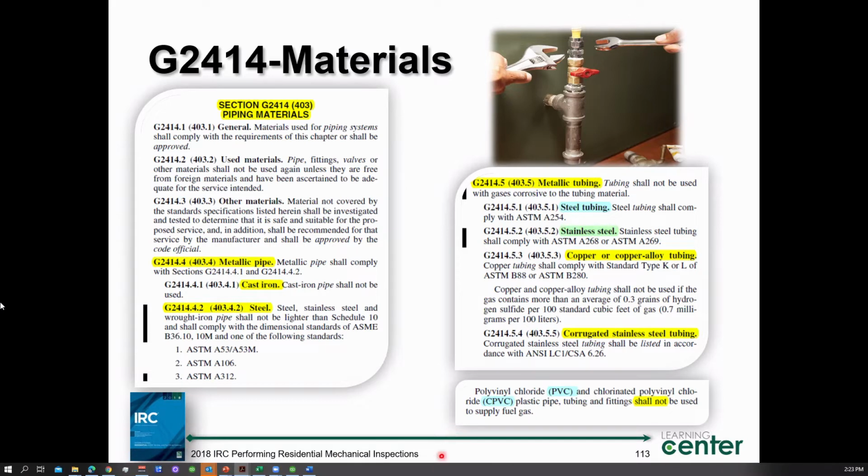When we talk about pipe, we talk about schedule, which is a very thick wall pipe, okay? We go anywhere from Schedule 120 to Schedule 80 to Schedule 40 to Schedule 20 to Schedule 10. Those are the pipe thicknesses based on schedule. Tubing size is measured in hundredths of an inch, which is by far a thinner material. But you can see that we use this, right?